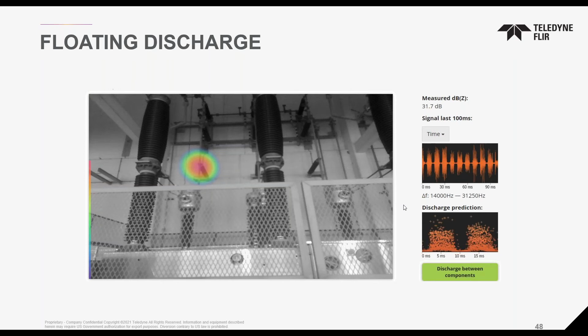Same thing here, it shows you the magnitude and tells you what it's seeing, like a discharge on the surface or inside the component. Here's a floating discharge, and here you can see it's saying discharge between components. There's a lot of electrical activity happening there, which could result in an arc flash.